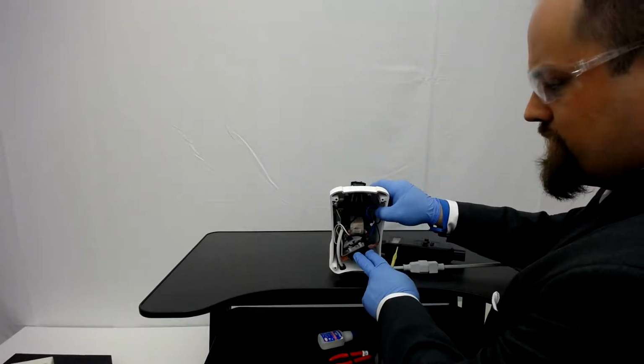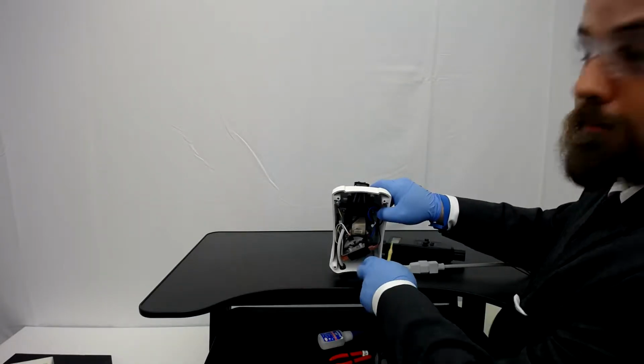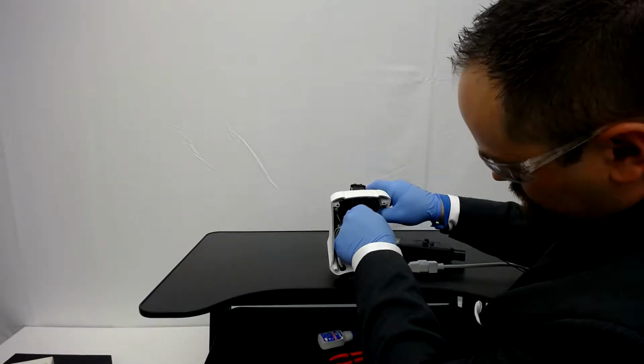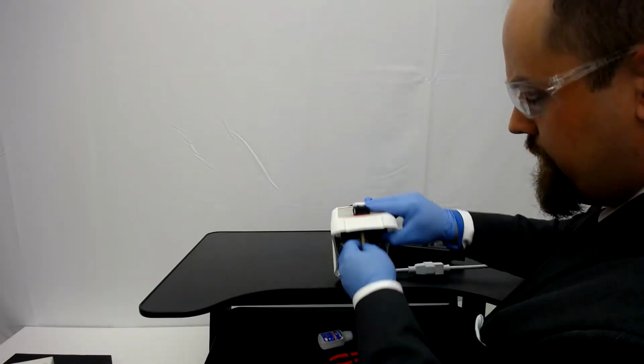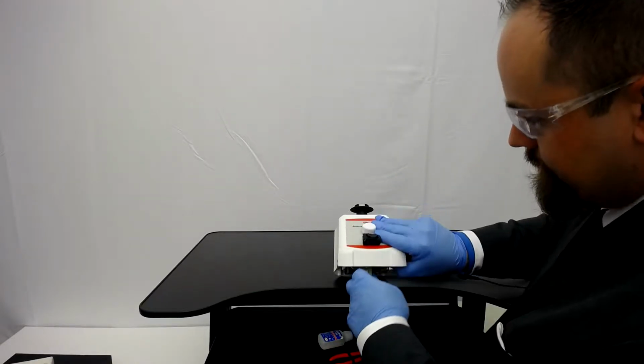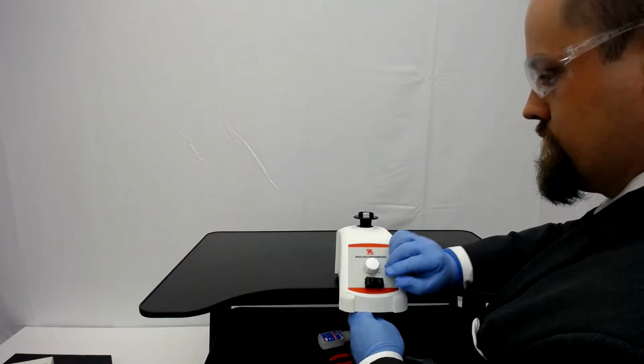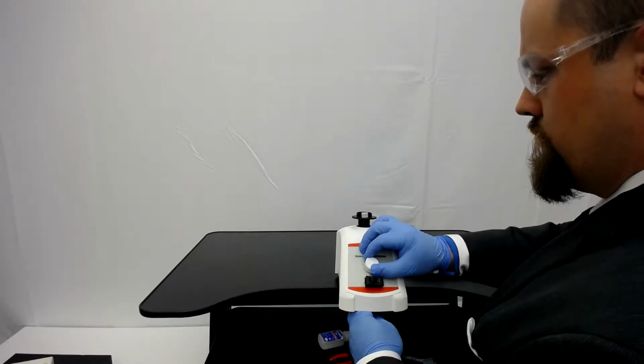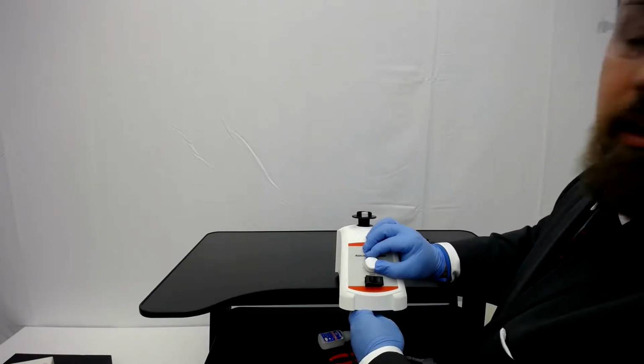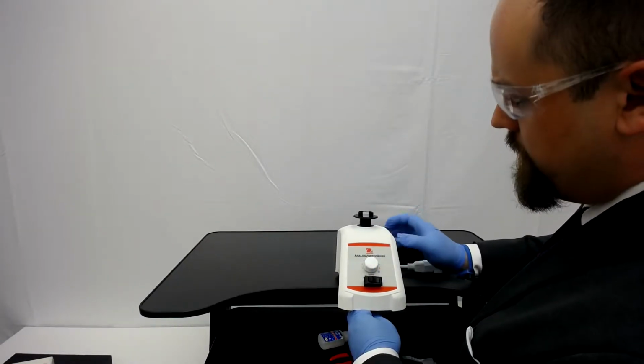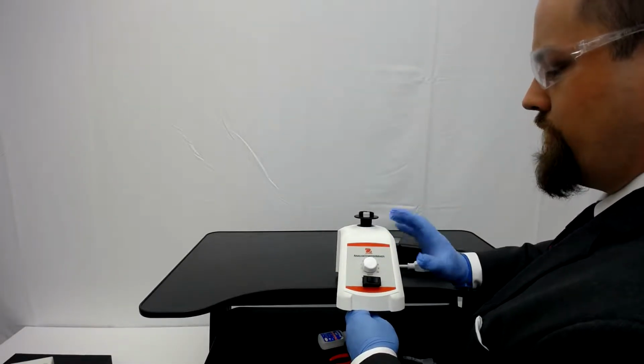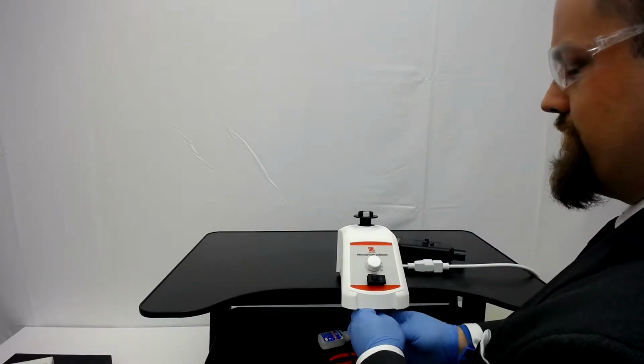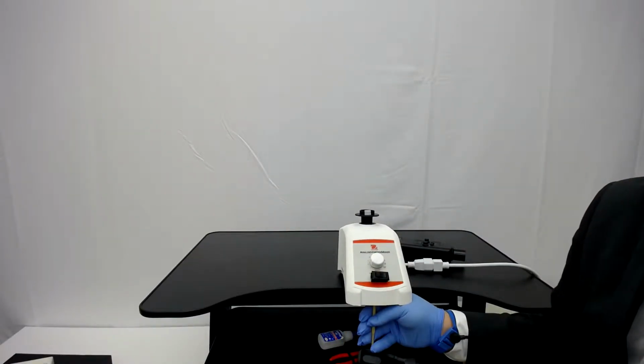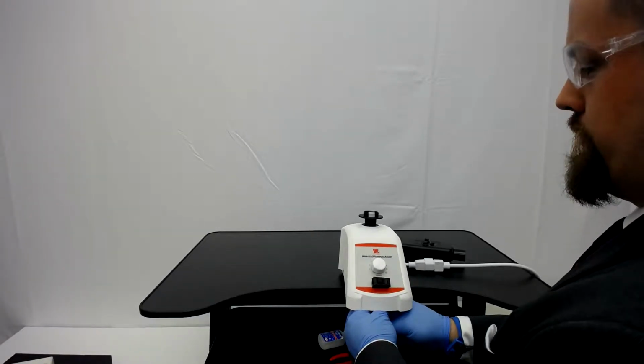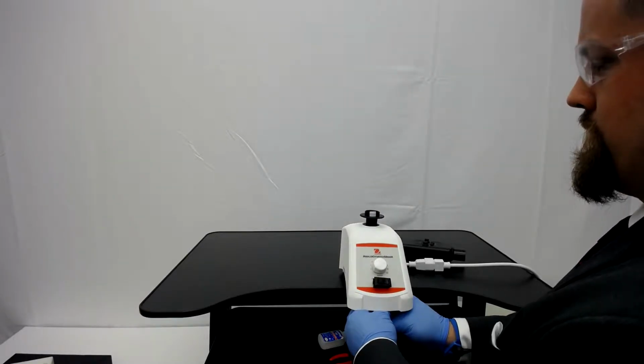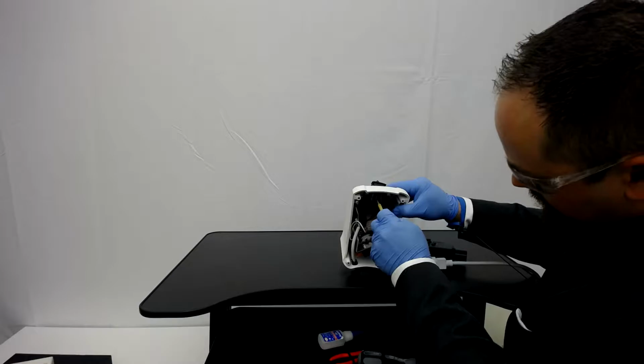As you put this down, make sure that the unit is not resting directly on the switch, as that can actually slow the motor a bit. So we're taking it off to the side. Turning the unit on. Just like before, we might need to jump start it. This particular unit has not been calibrated, but these units are much easier, much less touchy than the hot plate stirrers to calibrate. So we're going to start with this a little bit faster.